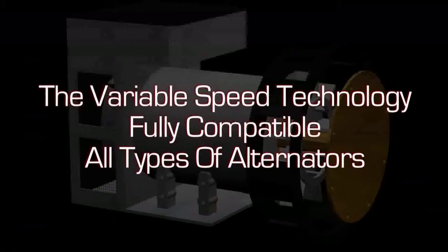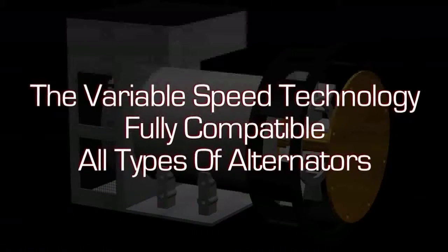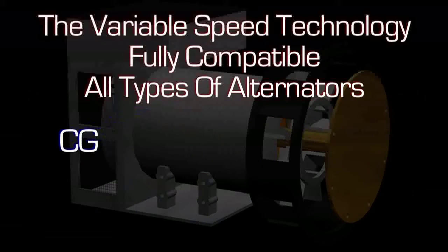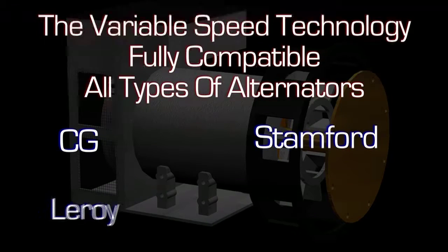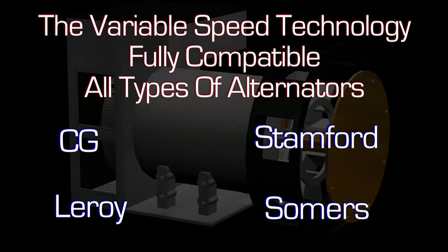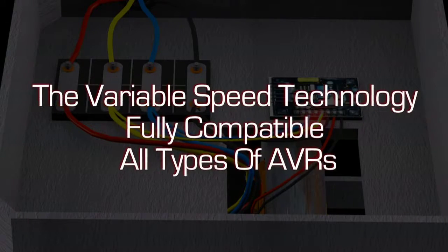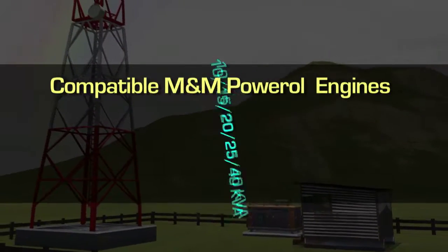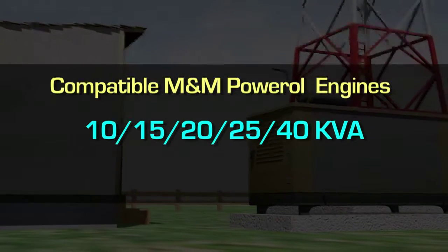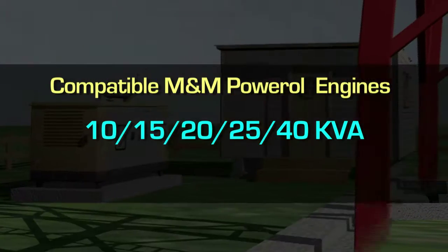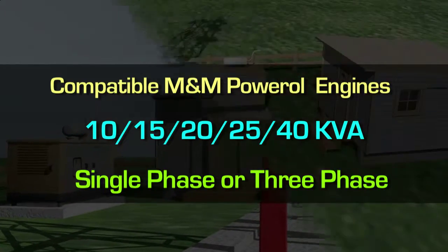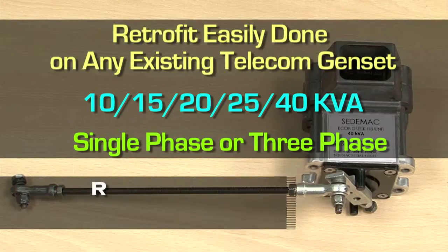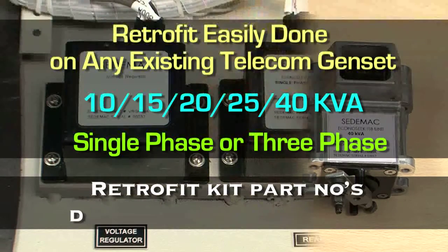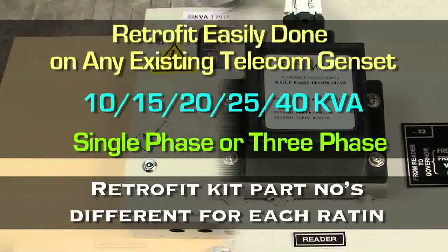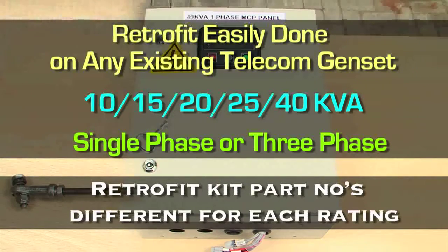The variable speed technology is compatible with all types of alternators: Crompton Greaves, Stamford, Leroy, Somers, etc. It also works with all types of AVRs and all Mahindra Powerol engines such as 10, 15, 20, 25 and 40 kVA rating, both single-phase and three-phase. However, note an important detail. The retrofit kit part numbers are different for different genset ratings.